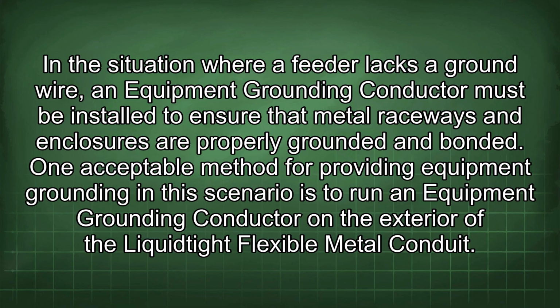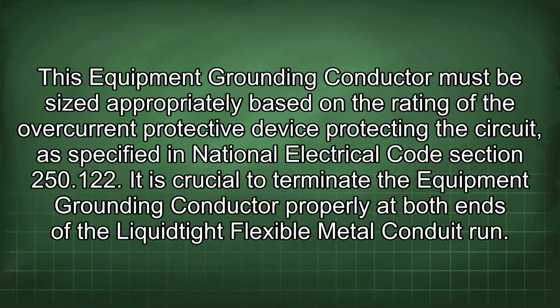One acceptable method for providing equipment grounding in this scenario is to run an equipment grounding conductor on the exterior of the Liquidtight Flexible Metal Conduit. This equipment grounding conductor must be sized appropriately based on the rating of the overcurrent protective device protecting the circuit, as specified in National Electrical Code section 250.122.